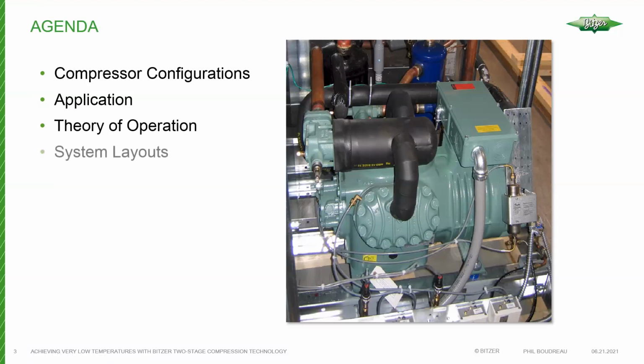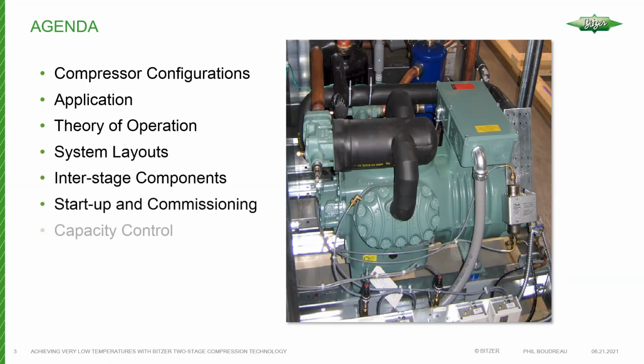So what we're going to look at today are, well, we saw the compressor configurations, but we'll talk about the configurations of how you can incorporate the compressor into the circuit, application, theory of operation, overall system layouts. So we get into subcooling versus desuperheating modes, the interstage components that are required. With two-stage compressors, because you have two stages that are essentially working in series, we need to have some auxiliary cooling injected into the process. Otherwise, the discharge temperatures just get super high, and we end up with a situation where we're burning up the very oil that we're trying to lubricate the compressor with.